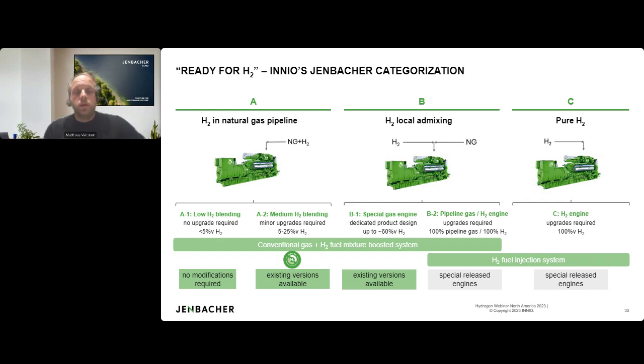Category B, if we look at that, we have also two subcategories, B1 and B2. We're looking at hydrogen concentrations of up to 60% by volume for category B1, or 100% for category B2. For category B1, up to 60%, we're still applying a pre-mixed system, adding the hydrogen and natural gas mixture right after the air filter via a gas mixing, gas dosing system, feeding it through the entire air system to the engine.